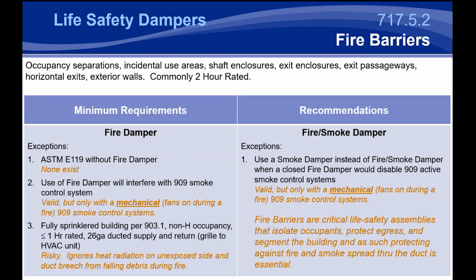But for all intents and purposes, you're going to need at least a fire damper requirement for these. Now, if your fire damper will interfere with the 909 smoke control system, by all means, it's very valid to remove that damper. You don't want a damper that's not tied in with the smoke control system to shut down and stop a building from, say, being able to exhaust smoke during the event of a fire. The only thing is most of the barriers where you're using these fire dampers are going to have a smoke requirement as well a lot of times. And with that smoke requirement, you're going to have the cost of a damper with an actuator no matter what you do. So removing the fire damper doesn't really add much cost savings. And it could potentially be a detriment to the system because even though you have a smoke control system in place, if you're seeing elevated temperatures of 250 or 350 degrees, typically that barrier is very close to a heat source. So adding the fire damper protection or thermostat that shuts down that damper will in fact help protect that fire barrier from withstanding that 2 hours.